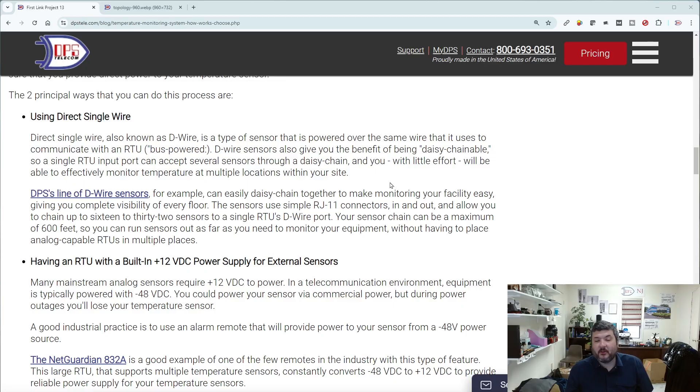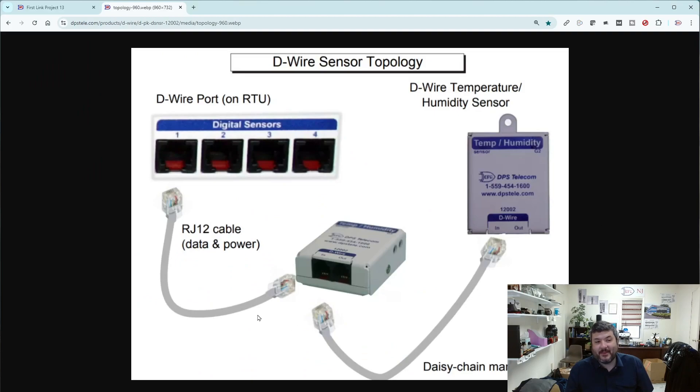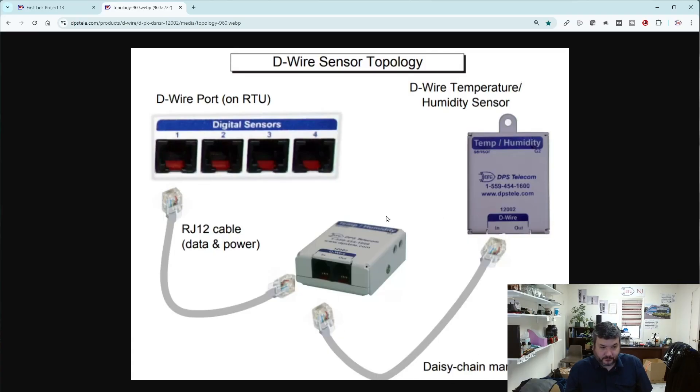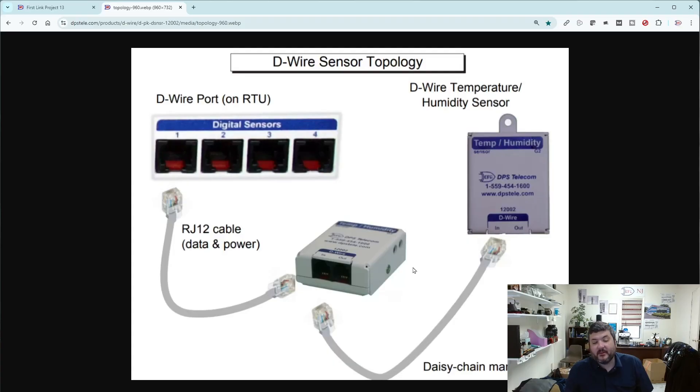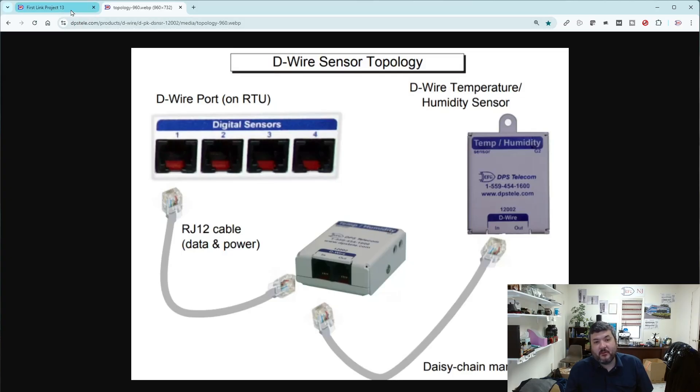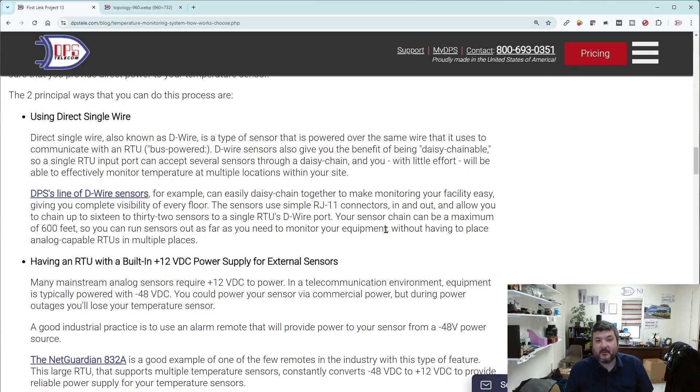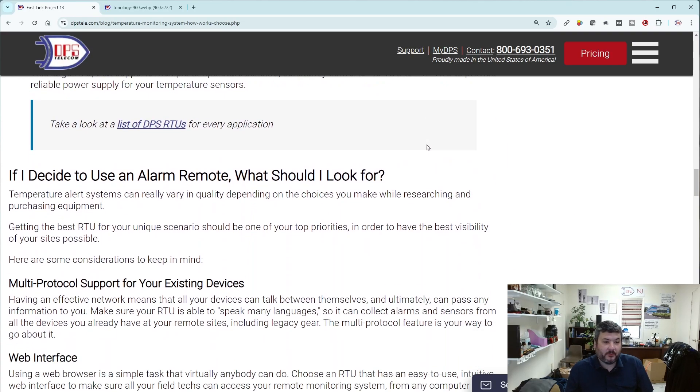The other piece is using what we call D-wire, or a direct single wire. This would be bus-powered sensors. The DPS variation looks like this: we have ports on our RTU on the top left of this diagram, and you would be connecting with a daisy chain from one sensor to the next. This is Cat5e cable where you put RJ12 ends on it and abandon one of the pairs. It's very convenient to customize lengths, but the critical piece is that it's not only daisy-chained but bus-powered. You don't need to worry about powering the sensors, and that can be a huge aid when you're talking about installing these things in an efficient way. You don't have to worry about huge amounts of install labor and DC to DC voltage conversion.